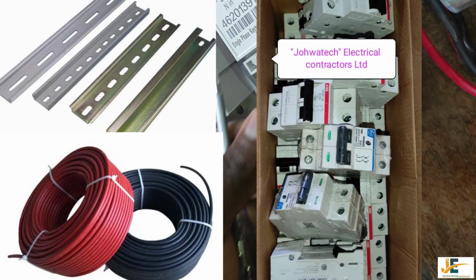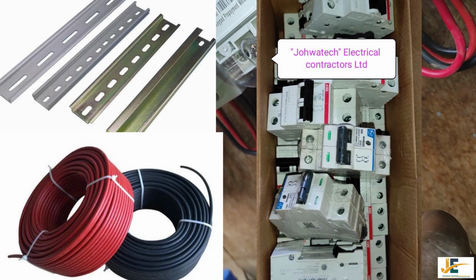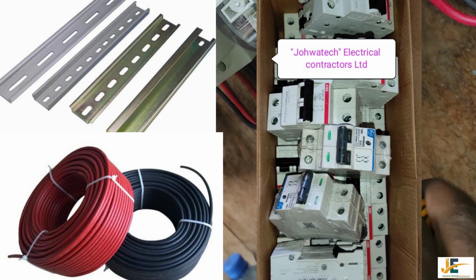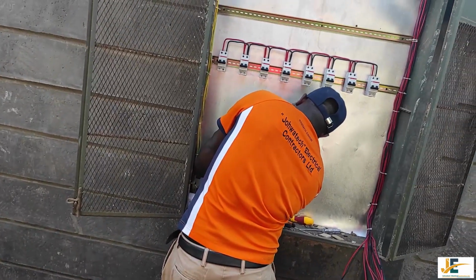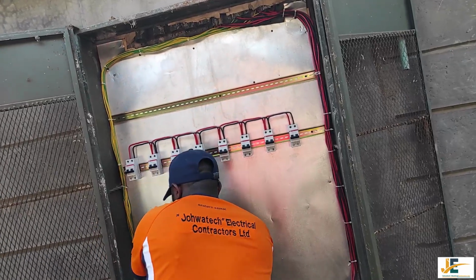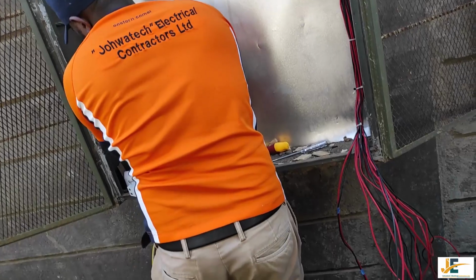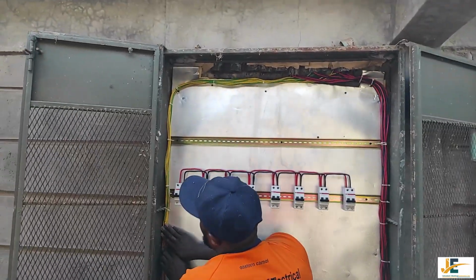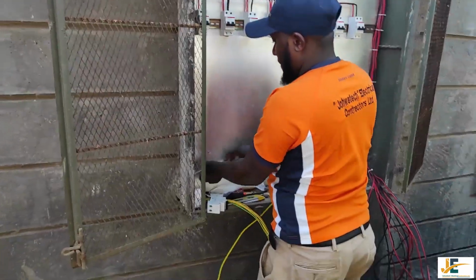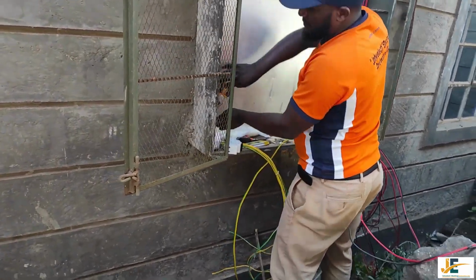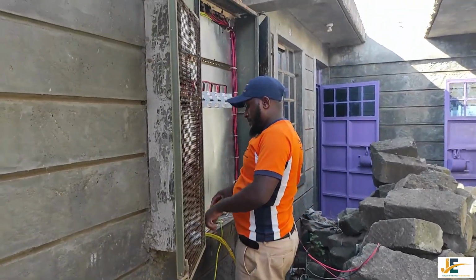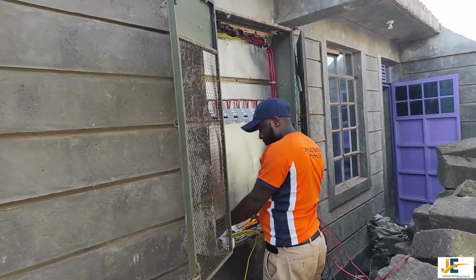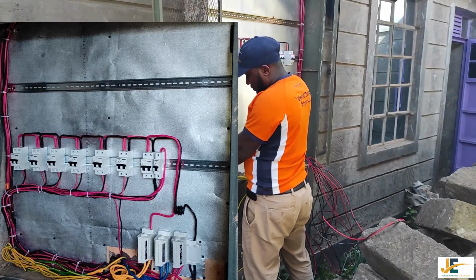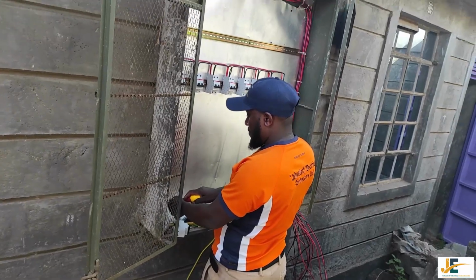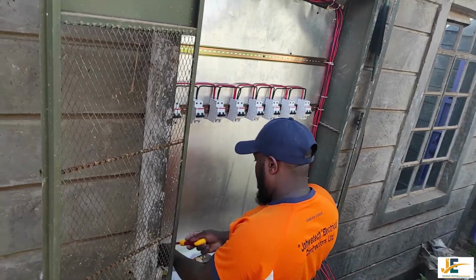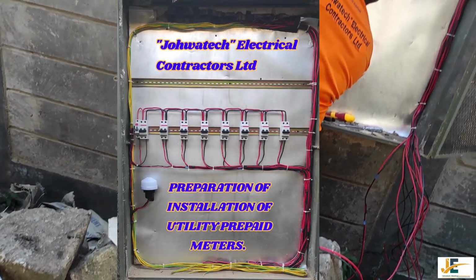Once we have all the electrical materials that we needed, that is DIN rail, MCB double poles, some few gypsum screws or self-tapping screws, the right size of cable, then we can start our mounting process. So we start by mounting the DIN rail, and our DIN rail, if it is longer than your meter box, you can cut to the desirable size. Once we mount our DIN rail on our meter box, and I always say it is good to have a good meter box. Our meter box or our utility meter box is supposed to be metallic, and if in case you find a meter box which has a wooden material inside, like 6-ply, 9-ply, you can reinforce it with a plain sheet or a flat sheet which is metallic.